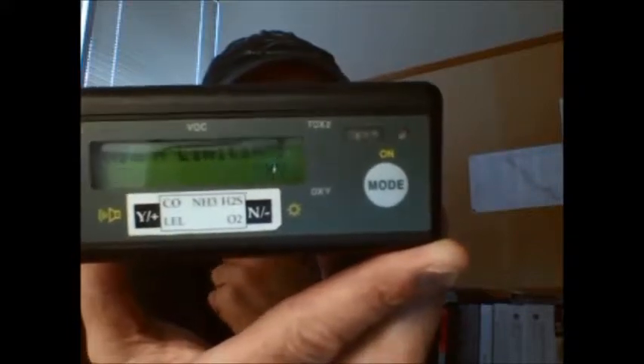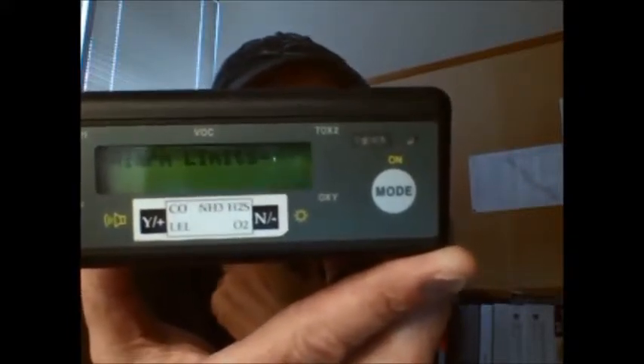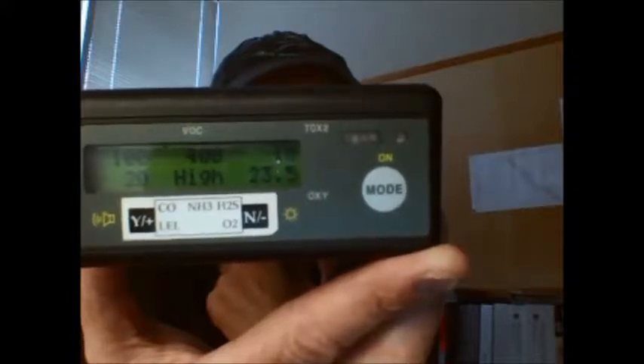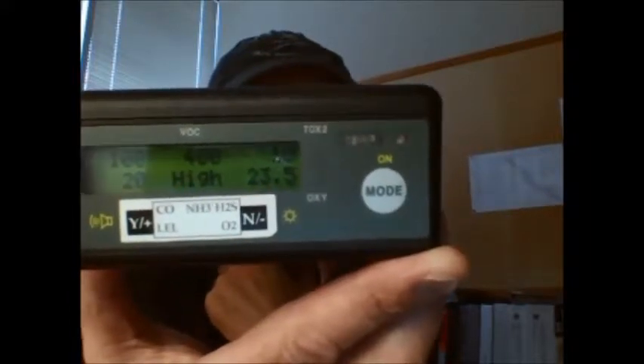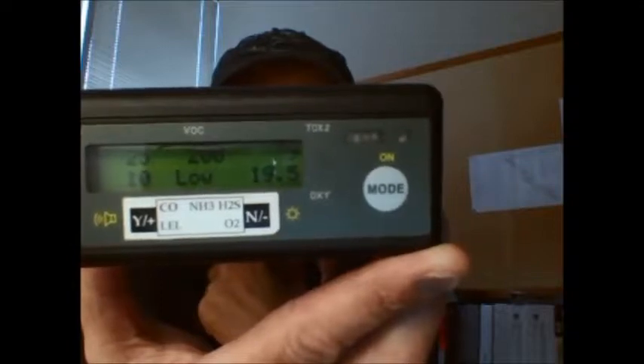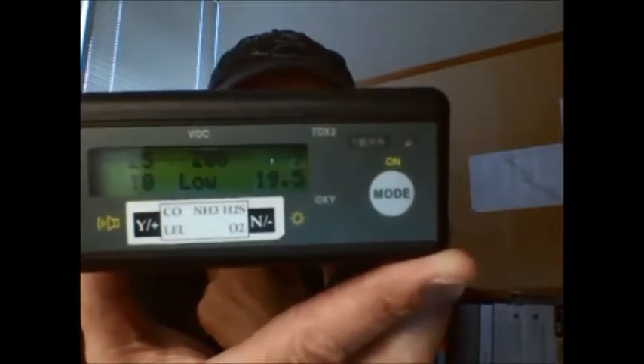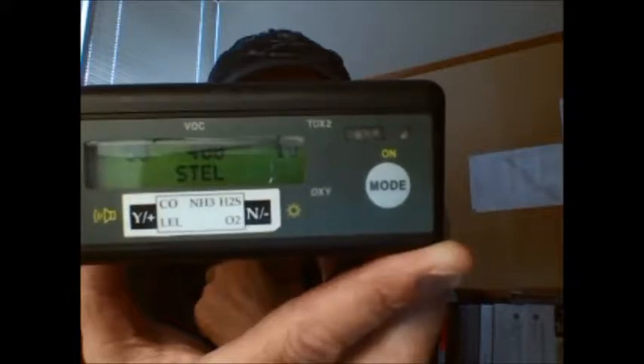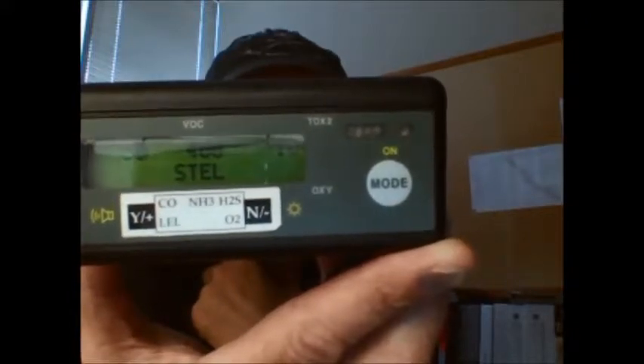Next, what you'll see through the screen are the alarm limits. And you must know what these alarm limits are. That's not what the alarm settings are, but the alarm limits. Those are the settings right there. And the rest of the data is as this device is booting up, it scrolls through all the data and it checks its battery life and some other information.